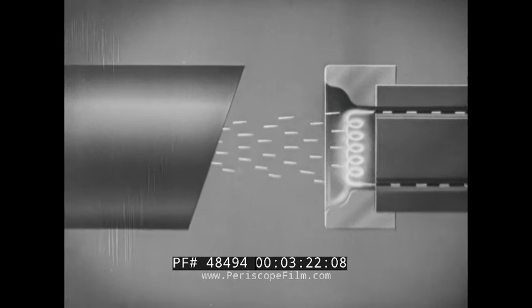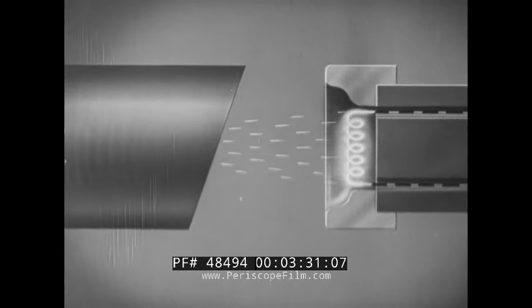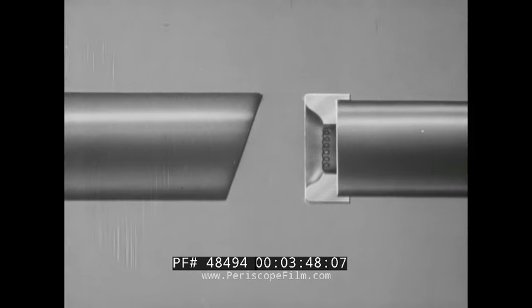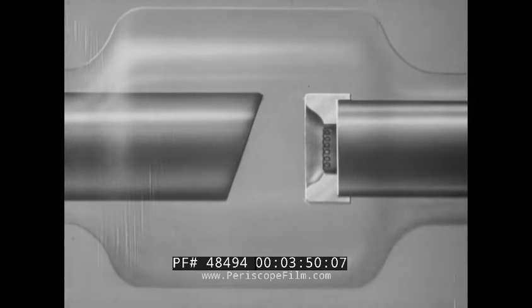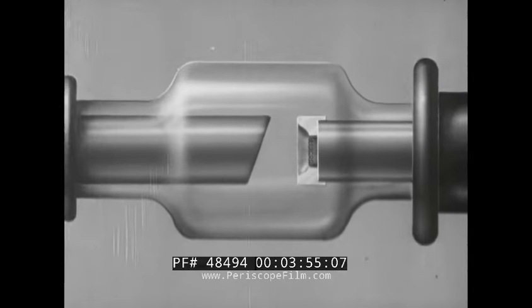The impact of the electrons on the anode generates heat. This is carried off by means of coolants and an anode of heat-conducting copper. The tungsten disk fused into the end of the anode is called the target. Tungsten is used because of its hardness and extremely high melting temperature. The filament cathode and the anode are sealed in a highly evacuated glass envelope. This becomes the x-ray tube.